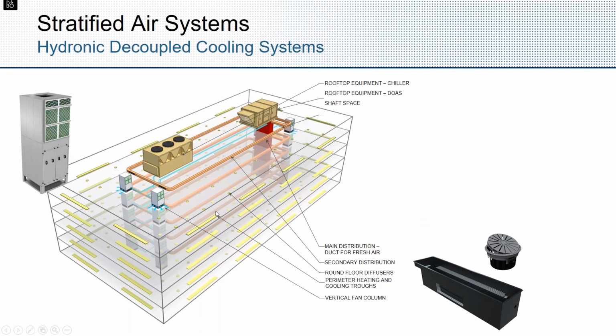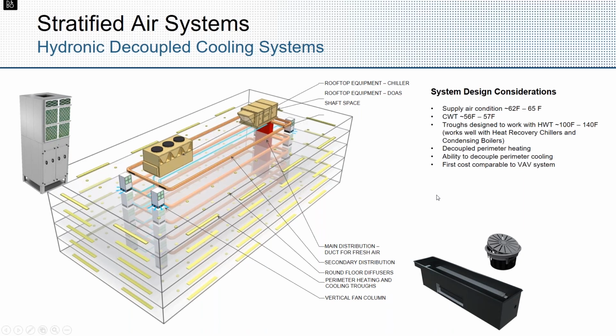And then here, there has been an evolution in underfloor air systems, moving from fan-powered terminals and putting a large amount of fans underneath the floor, to shifting to these natural convective troughs, where each of the active sections underneath the floor grill utilizes space return air that falls down into this plenum and then heats up in the case of heating. For cooling, you can have a VAV damper that just modulates to condition the perimeter. So again, these work quite nicely with condensing boilers. 100 to 140 degrees is pretty typical of incoming water temperature to these troughs to handle your 750 BTUs to 1 MBH per foot along the perimeter.